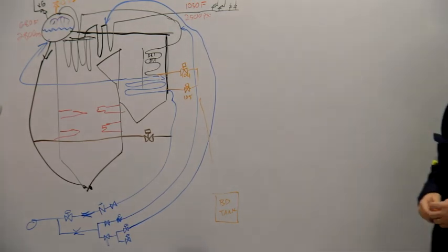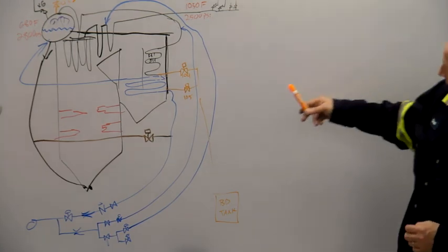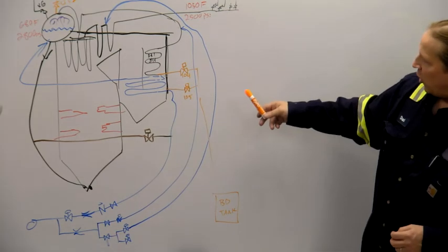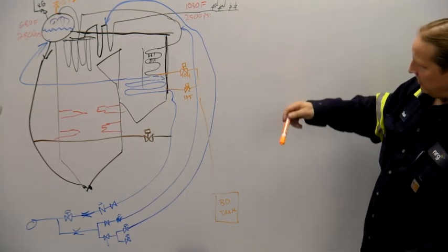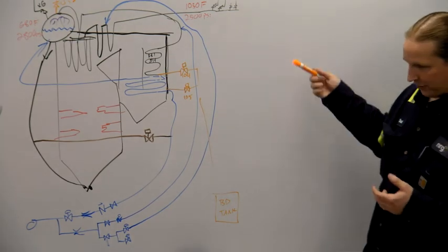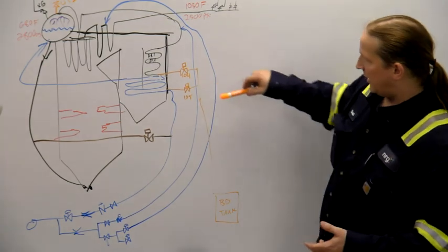So if the pressure gets too high in the primary superheat, those 104, 105 blowdown tank lines open up. These are not protected from overpressure. These are open during startup, and we pinch back on them and finally close them after the unit syncs, because they're just giving a flow path and a way to drain water out of the system.